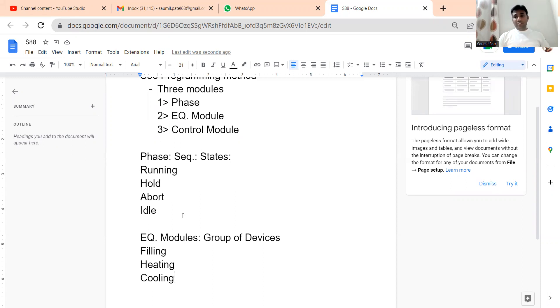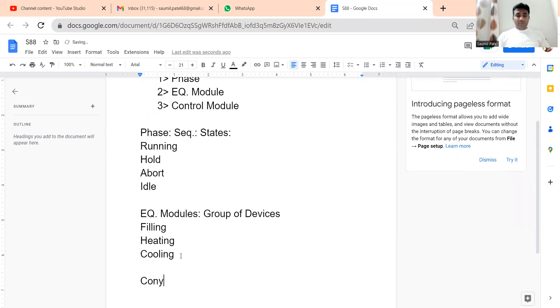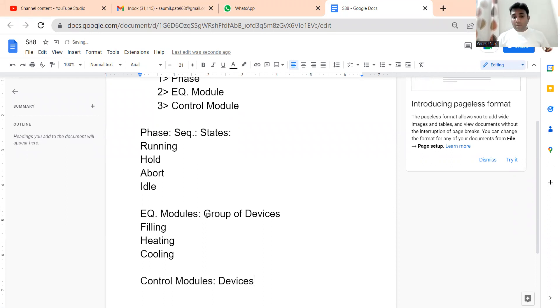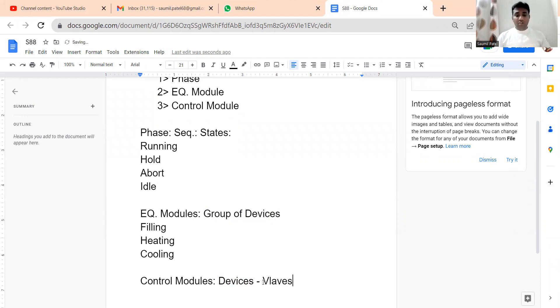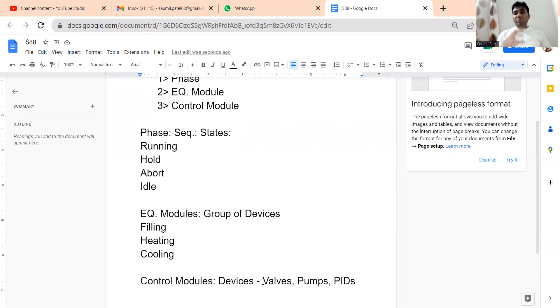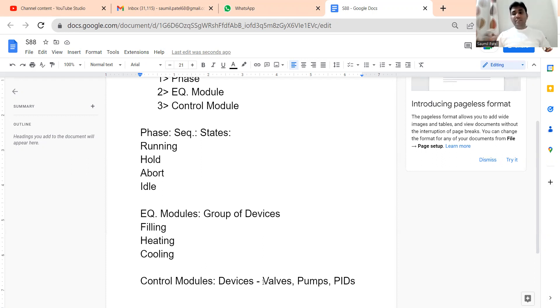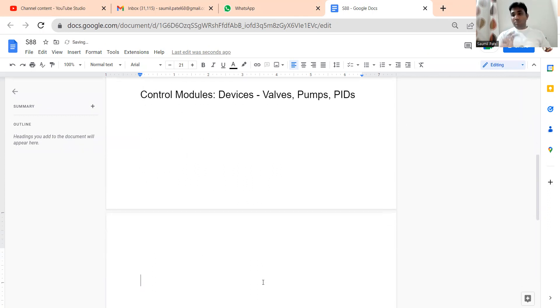Equipment Modules directly control some devices to perform these functions; those devices can be valves and pumps. Phase is your sequence, Equipment Module is your functions — a group of devices doing those functions. Control Modules, on the other hand, are individual particular devices. The devices can be a valve, a pump, a PID, a VFD. You need to program each and every Control Module in your S88 standard.